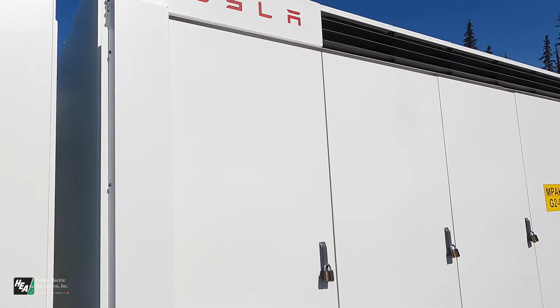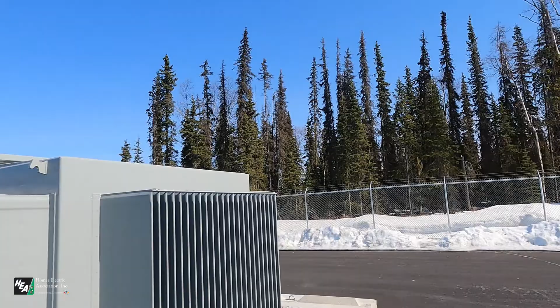The BESS includes an integrated heating and cooling system to keep the batteries at their optimum temperature. To further increase their longevity, HEA plans to avoid fully charging and discharging the batteries under normal operation, since that causes excess heat, which leads to battery degradation. HEA plans on running its battery at a charge level between 70 and 85%, so that we have near maximum ability to provide power to the system without impacting the life of the batteries. In 15 years, the batteries should be at 87% of their original capacity, versus 70% if the batteries went through daily full charge and discharge cycles during that time.